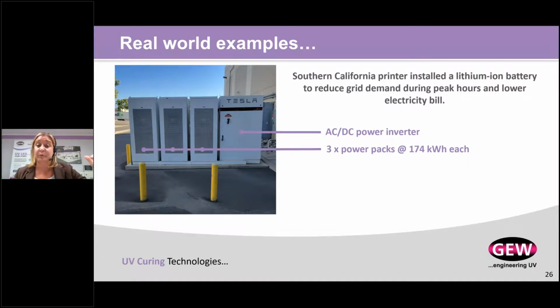That raises their peak demand, which is then billed as a penalty or as part of their demand rate. So their electricity bills go up significantly because they're switching all of their equipment on at the same time on Monday morning. So what they did is stagger it. They bring guys in earlier, before the peak demand time starts, and stagger how they bring those three presses online.